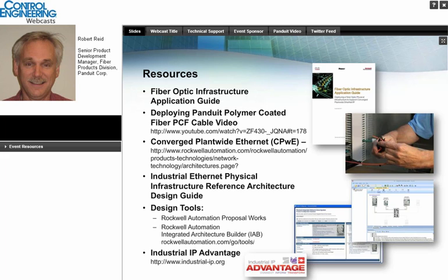Good. When should one use patch panels in a project? Are there mini patch panels for small fiber connection points? How does that work? Yeah, in general, from what we've seen in the industrial market, the patch panel is not always required or valued. If I have an industrial automation control panel where there are no changes in the panel, as an example, I would recommend, and I think a lot of people are going to do, direct attach. The connector will be terminated and plugged into the electronics.